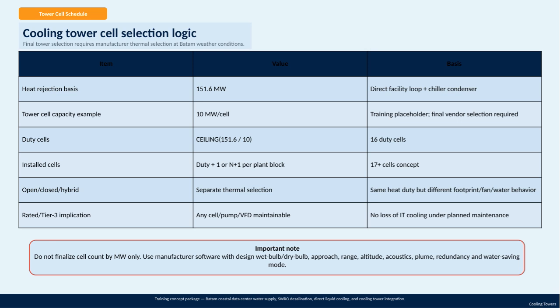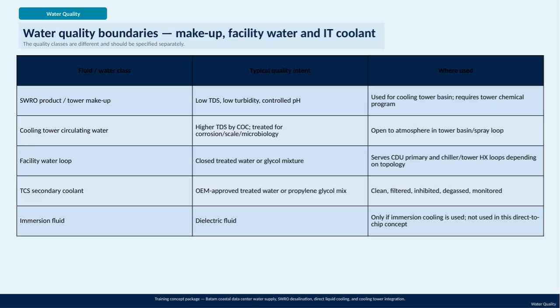Finally, a critical note: never finalize a cell count based solely on megawatts. You must use manufacturer software that factors in design wet bulb and dry bulb temperatures, approach, range, altitude, acoustics, plume, redundancy, and water-saving modes. This comprehensive evaluation ensures the cooling tower system is both efficient and reliable under all operational conditions. Let's take a closer look at water quality and its importance in different parts of our system.